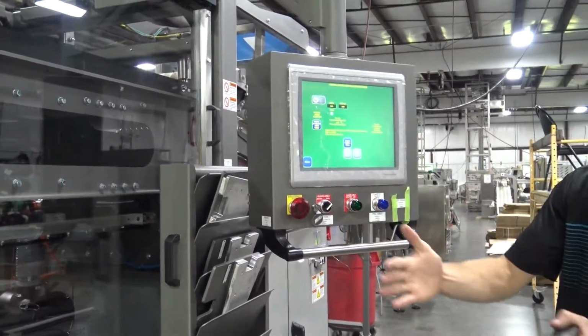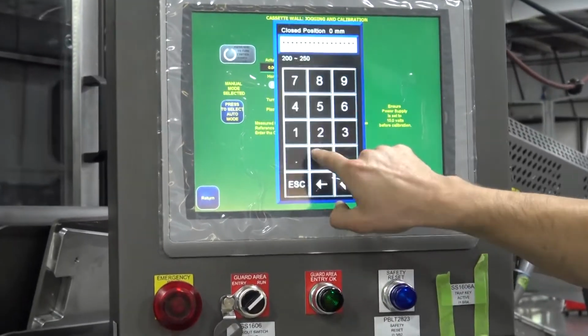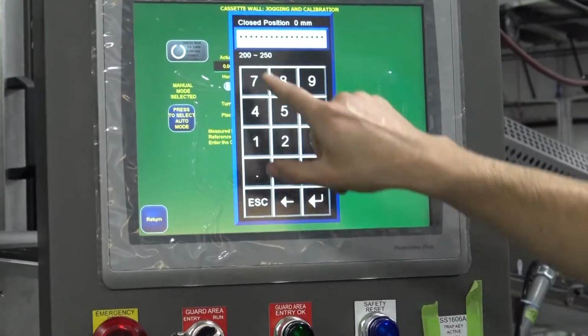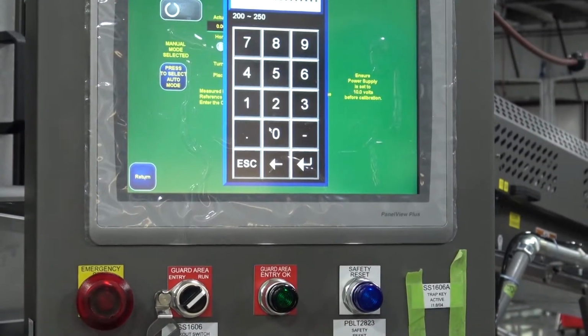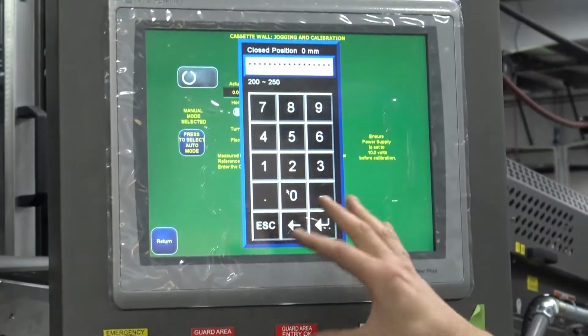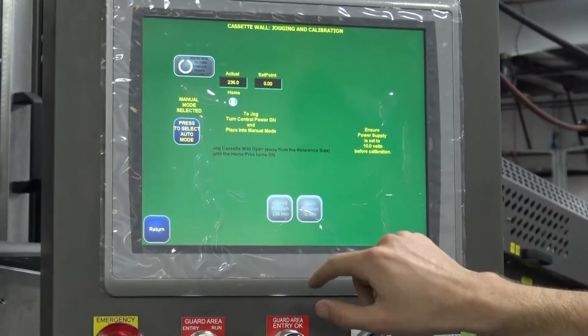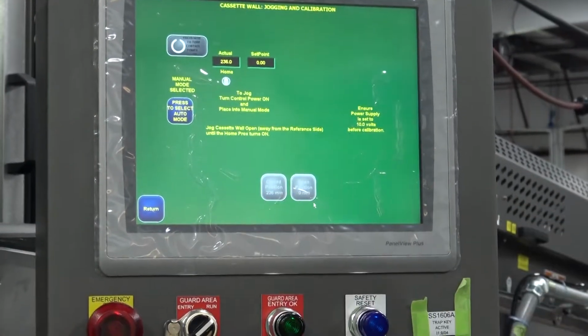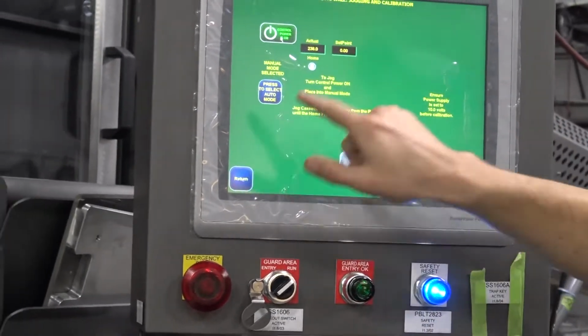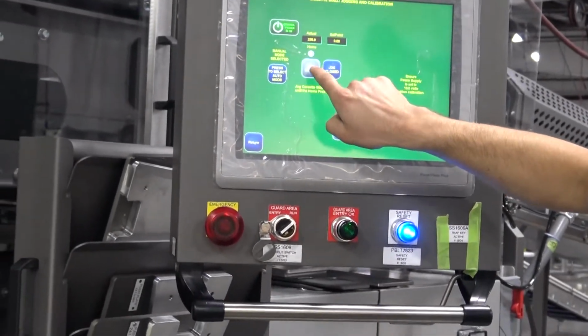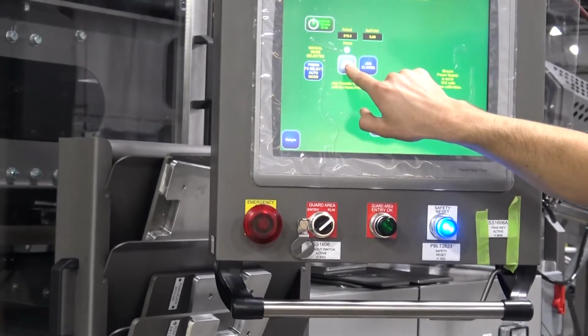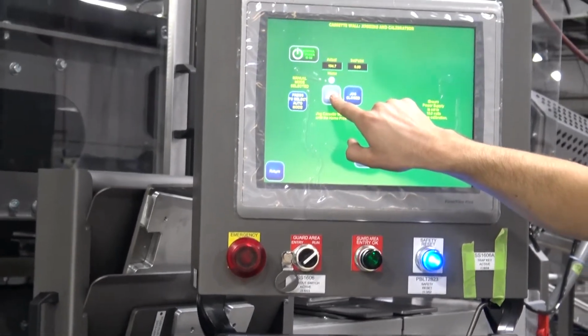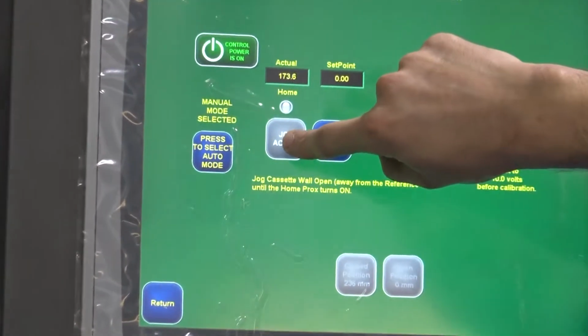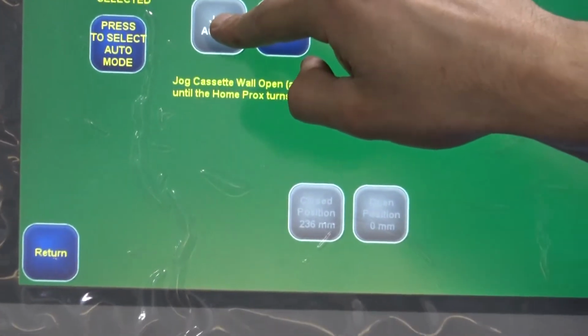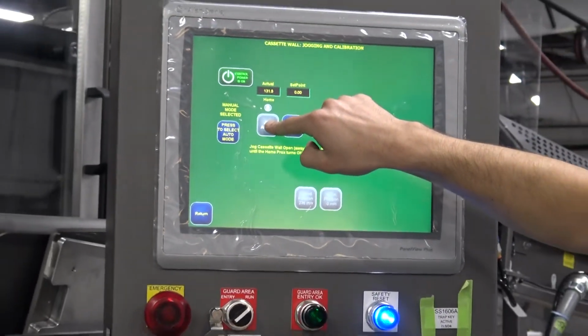So I've jogged it all the way closed, and now I get this button, closed position. And then you're going to look at the range that's acceptable, which is 200 to 250. The measured position we got was 236, so that is kind of a double check that we're doing something right. So 236, we're in the range, we're okay. It accepted that value. Now it wants us to jog the wall all the way open and then take the measured value again. So I return control power, I get my jog buttons, and I want to jog all the way open. There's nothing that's going to interfere in this case, so just leave your finger on the button, jog it all the way open, and you'll see the input box where you can input the new measured position pop up when it's ready. So the far wall is jogging away from us for the wide position measurement.